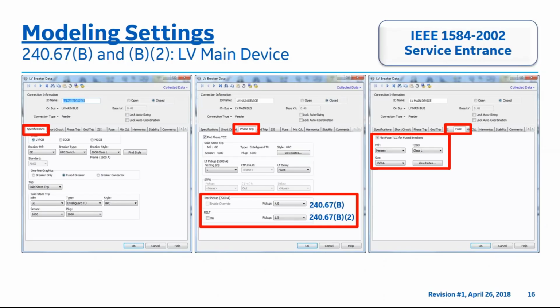If the time current curve settings need to be adjusted, then the pull-down menu can be utilized to move the time current curve from the left to the right with a maximum value of 10.0 to achieve proper coordination and/or selective coordination while clearing arcing faults per the 240.67 requirements of the 2017 NEC. Right below the instantaneous pickup is GE's RELT that can be checked on in this Phase Trip tab. GE's term that stands for Reduced Energy Let Through for the maintenance switch per 240.67B2 defines the pickup value in this section of the modeling software. For plotting the fuse on the right-hand side of the screen, you can select to plot the time current curve for the fuse type per the EasyPower menu options available in the software modeling application.